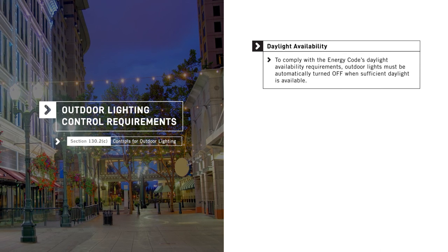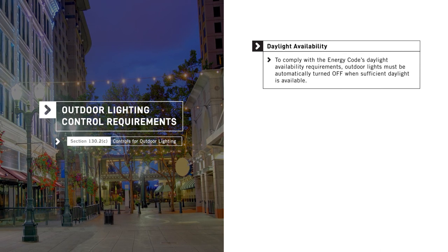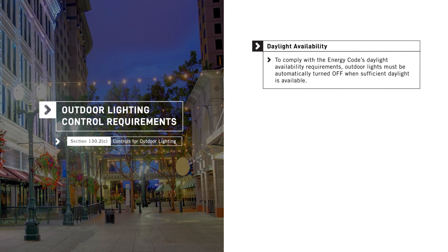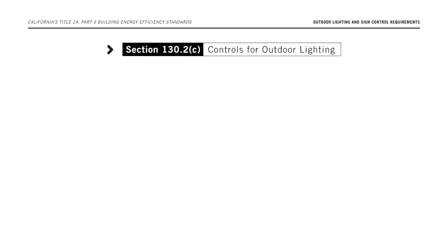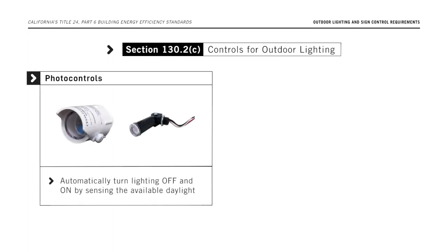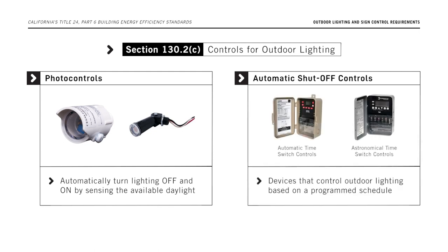To comply with the Energy Code's Daylight Availability Requirements, outdoor lights must be automatically turned off when sufficient daylight is available. Two types of lighting controls meet this requirement: one, a photo control, which automatically turns lighting off and on by sensing the available daylight; and two, an automatic shut-off control, which controls outdoor lighting based on a programmed schedule. One type of automatic shut-off control, called an astronomical time switch, includes a feature that adjusts the programmed schedule according to local sunrise and sunset times.